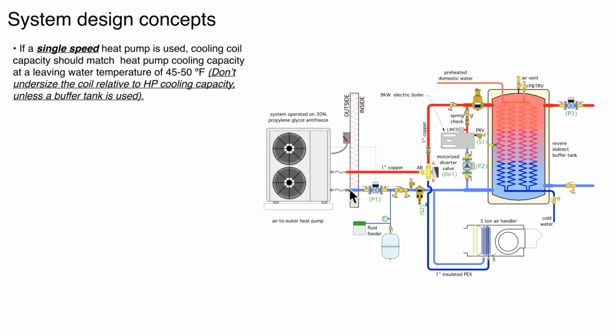Now, single speed heat pumps. Cooling capacity on the coil, you have to match the coil to the nominal cooling capacity of the heat pump. Again, we don't want to put a 5-ton or even a 4-ton heat pump on a 2-ton air handler. You're simply going to be cycling the heat pump on and off quite a bit. So a buffer tank could be used.